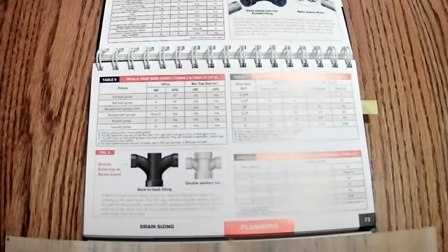Okay, so basically, according to the IRC, you're allowed to have on a horizontal line 20 fixture units and 48 on a vertical. Now, the UPC number of drainage fixtures says 35 fixture units, but there's a note there, D, and D says a maximum of 3 toilets on a horizontal branch.